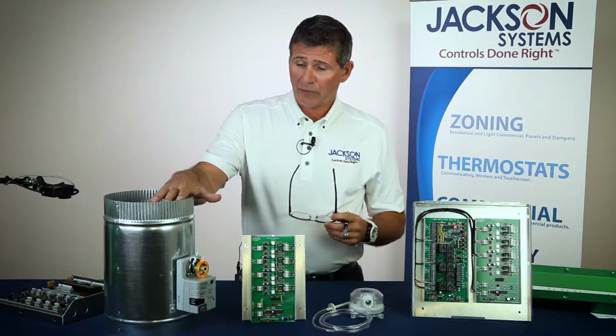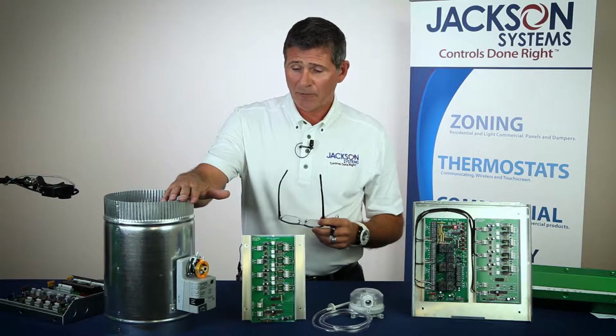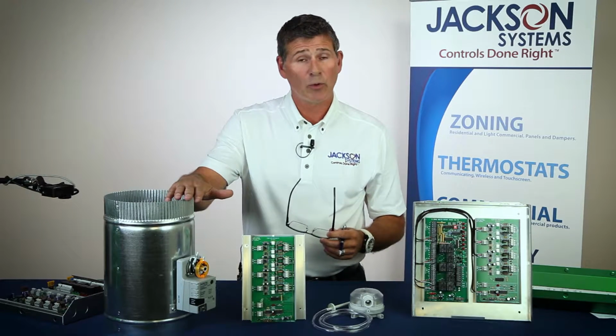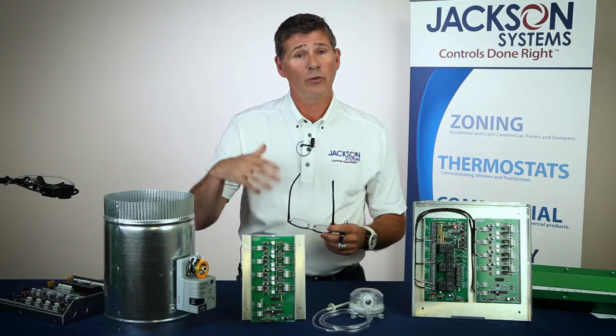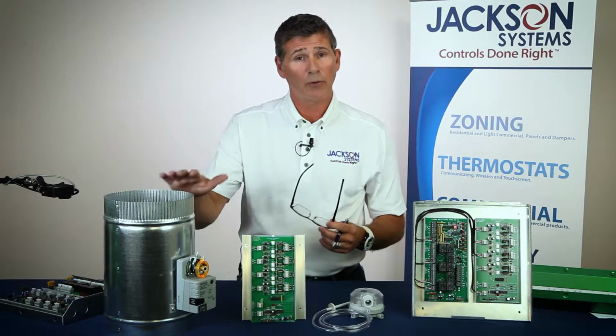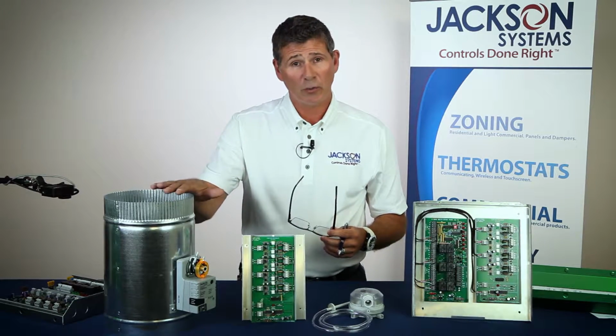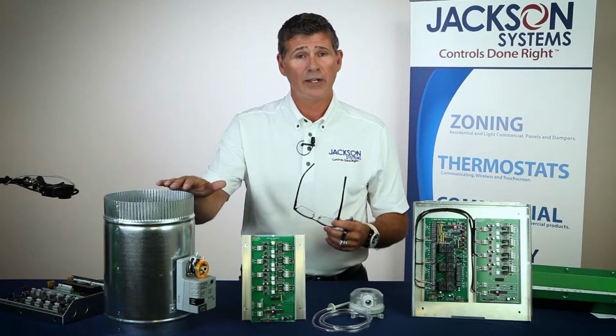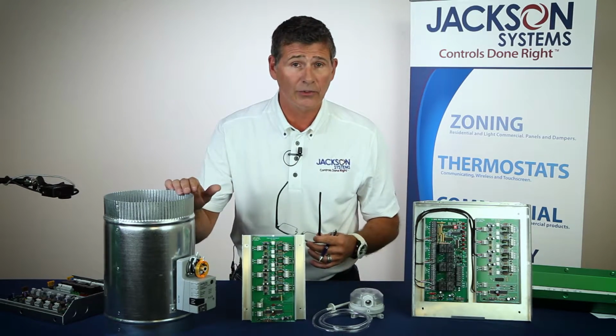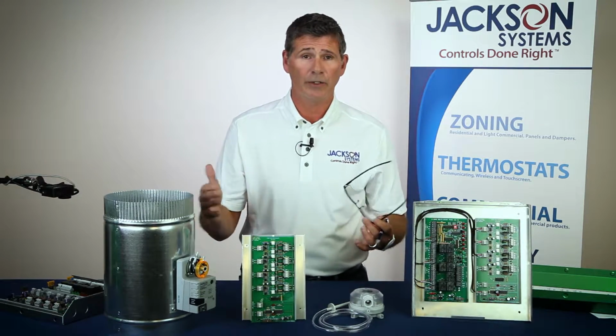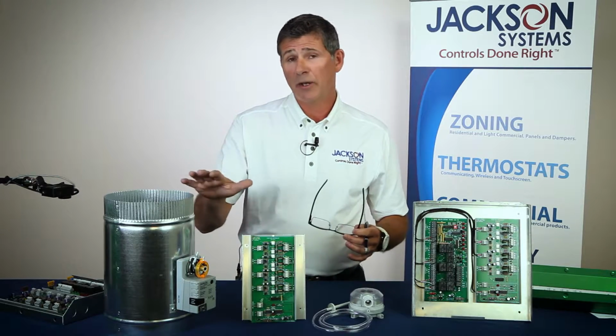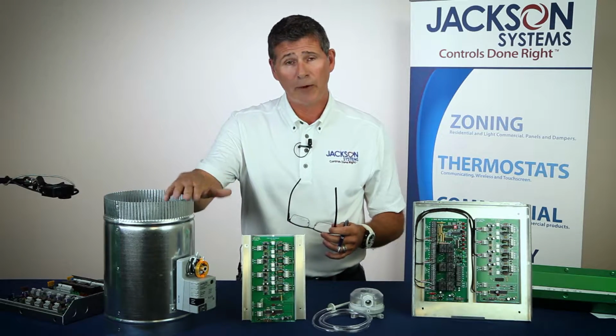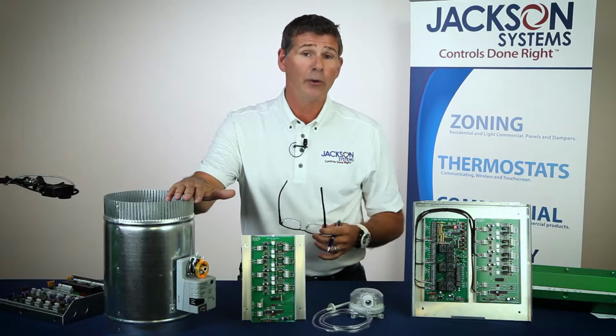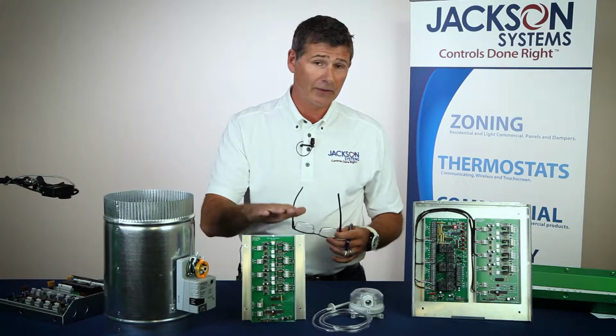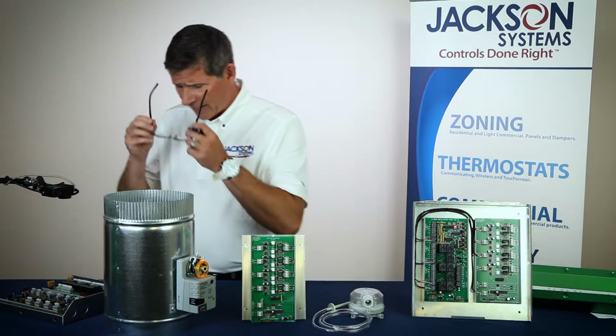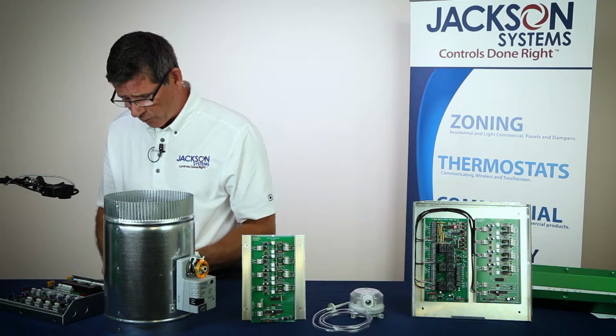So I've got a damper here in front of us. This is our 3-wire damper with a Belimo actuator, floating point actuator that we use. Belimo builds this specifically for us. And this is what you're going to want to use. It will work with a 3-wire damper if by chance you may have a Honeywell system already set up, like with their 4-zone system. You're going to want to make sure that you've got a 3-wire power open, power closed damper already installed if you're going to be using this system. So again, looking at it, you're going to notice right away, because again, we've pre-wired this.